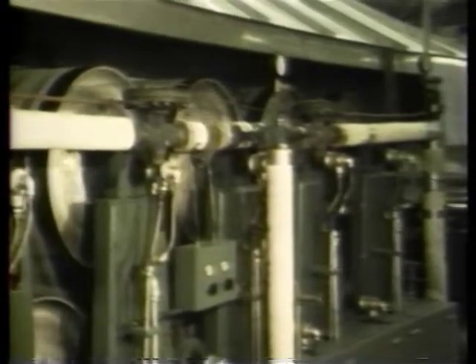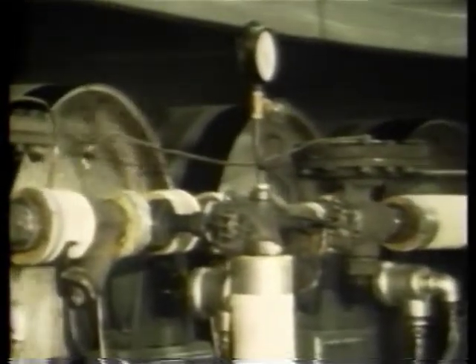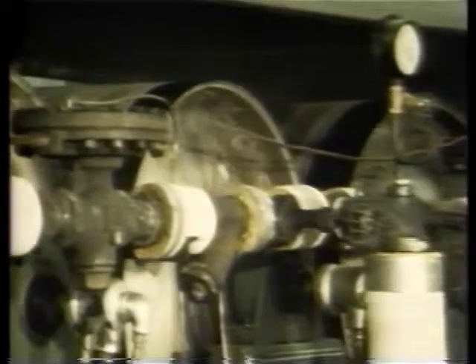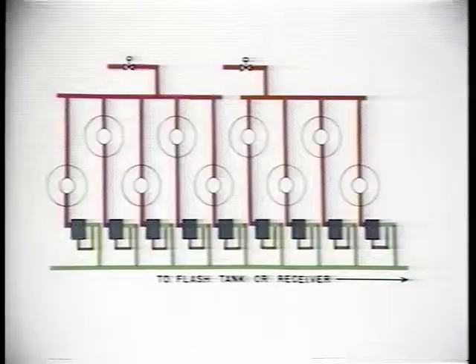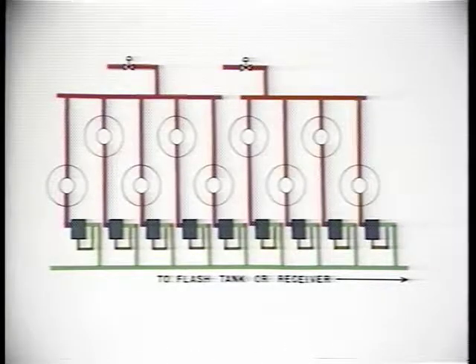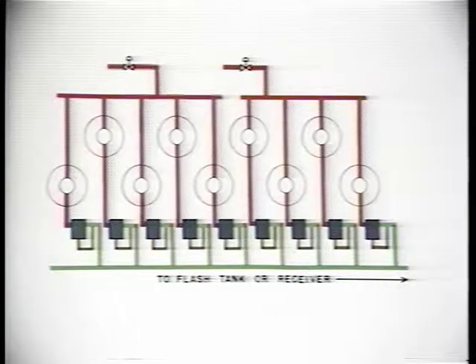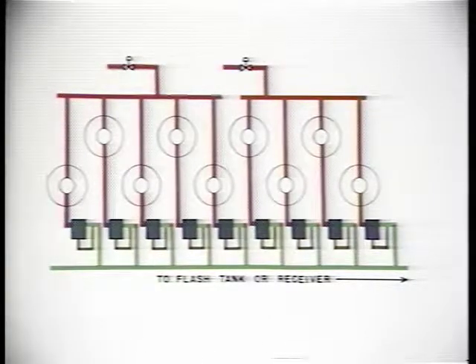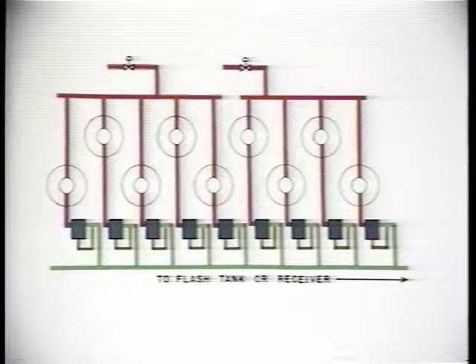Some steam-heated rotary cylinders found in the textile industry are not conducive to the HeatTech system approach. Slashers, for example, may be grouped with a single control valve for several cylinders. Many of the benefits of the HeatTech system can be obtained by using rotary siphons and differential controllers with the bypass steam piped to the condensate return line.